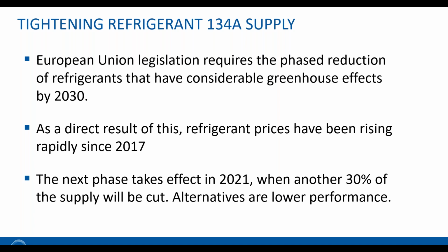operational today. So the change to alternatives, on the other hand, will mean potentially the loss of performance for existing sites, and especially for future sites. That means potentially relatively bigger mechanical units, bigger chillers, bigger air conditioning units to drive the same amount of cooling capacity. Again, the message here is that for both operational sustainability and also for environmental sustainability, as a green message for corporate responsibility, liquid cooling offers a way out of this squeeze.